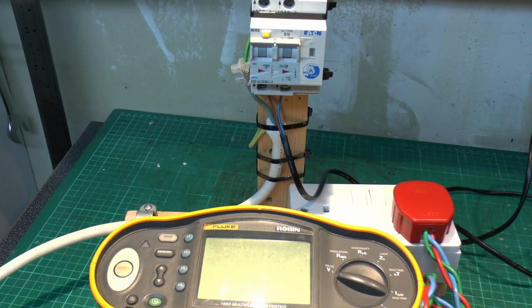And we're also going to have a look at the overvoltage part of it, because according to the instructions supplied, it will trip if the voltage is too high, more than 270 volts in the case of the one we've got. So let's go and have a go at that in the other workshop. Now let's have a go with the overvoltage thing on this one.